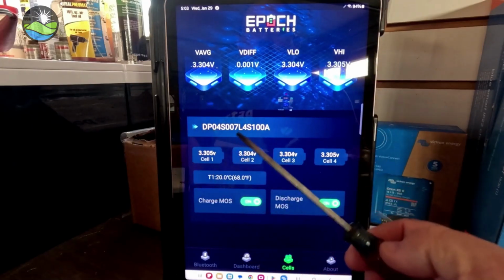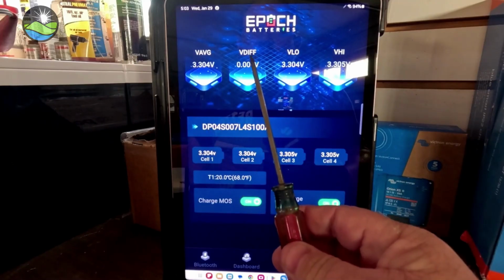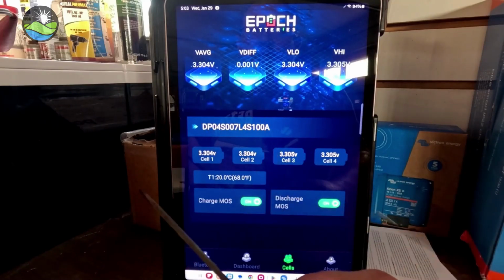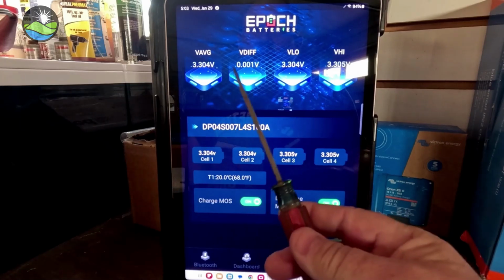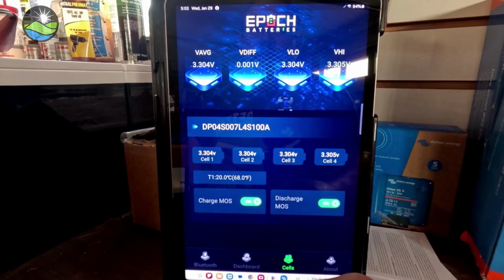What it's mostly useful for is looking at the voltage difference. If the cells and batteries are in balance, especially at the top of the charge—what they call the upper knee, around 14, 14.1, 14.2 volts—you want to check how far apart they are. You might see 30 millivolts, 0.030 volts differential at the top of charge, because the cells begin to split in the upper knee and upper voltage.